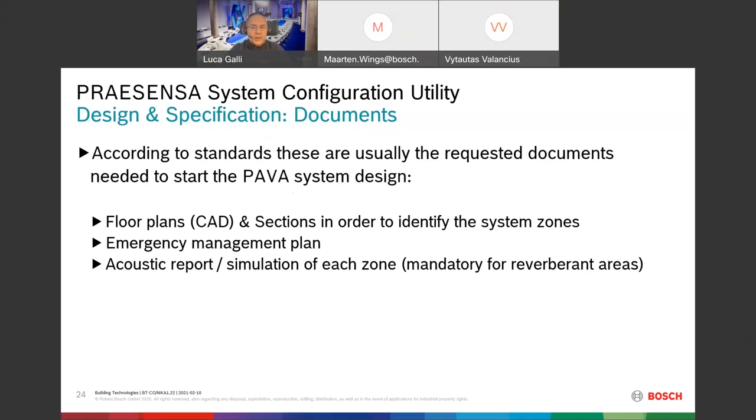Of course, an emergency management plan is needed in order to define the way to do the evacuation of the people. And last but not least, it is also not mandatory, but really, really useful, and is asked by the standards, to have an acoustic report or simulation for each zone, especially for all those zones that have some trouble in terms of acoustic behavior. For instance, if we have reverberant areas, it is really important to understand the acoustic behavior of the rooms. So starting from these points, these remarks, we can design the system in the right way.